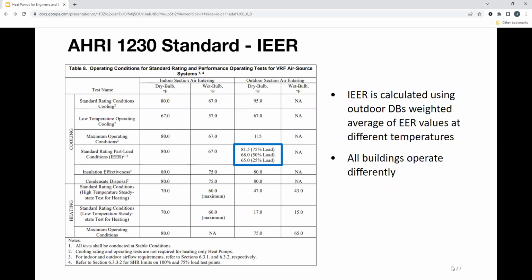Now, we get this question a lot. The number one performance question is, hey, at this temperature, what is your efficiency, right? You have 80, 67 and all the published data associated with certain EER, IEER, and COP levels. But those temperatures are not seen that often year round. So you've got to come up with a way to better describe how a heat pump operates. And as far as published data goes, IEER is the best way to determine that. So the testing conditions at 100% are 95 degrees, and then you have your weighted EER values based on temperature bin data. So 75% load is around 81.5, 50% is at 68, and then 25% load is at 65. Those EER values are all taken together, and you come up with an IEER value. When you talk about part load efficiency, this is a great way to determine how efficient this piece of equipment is.